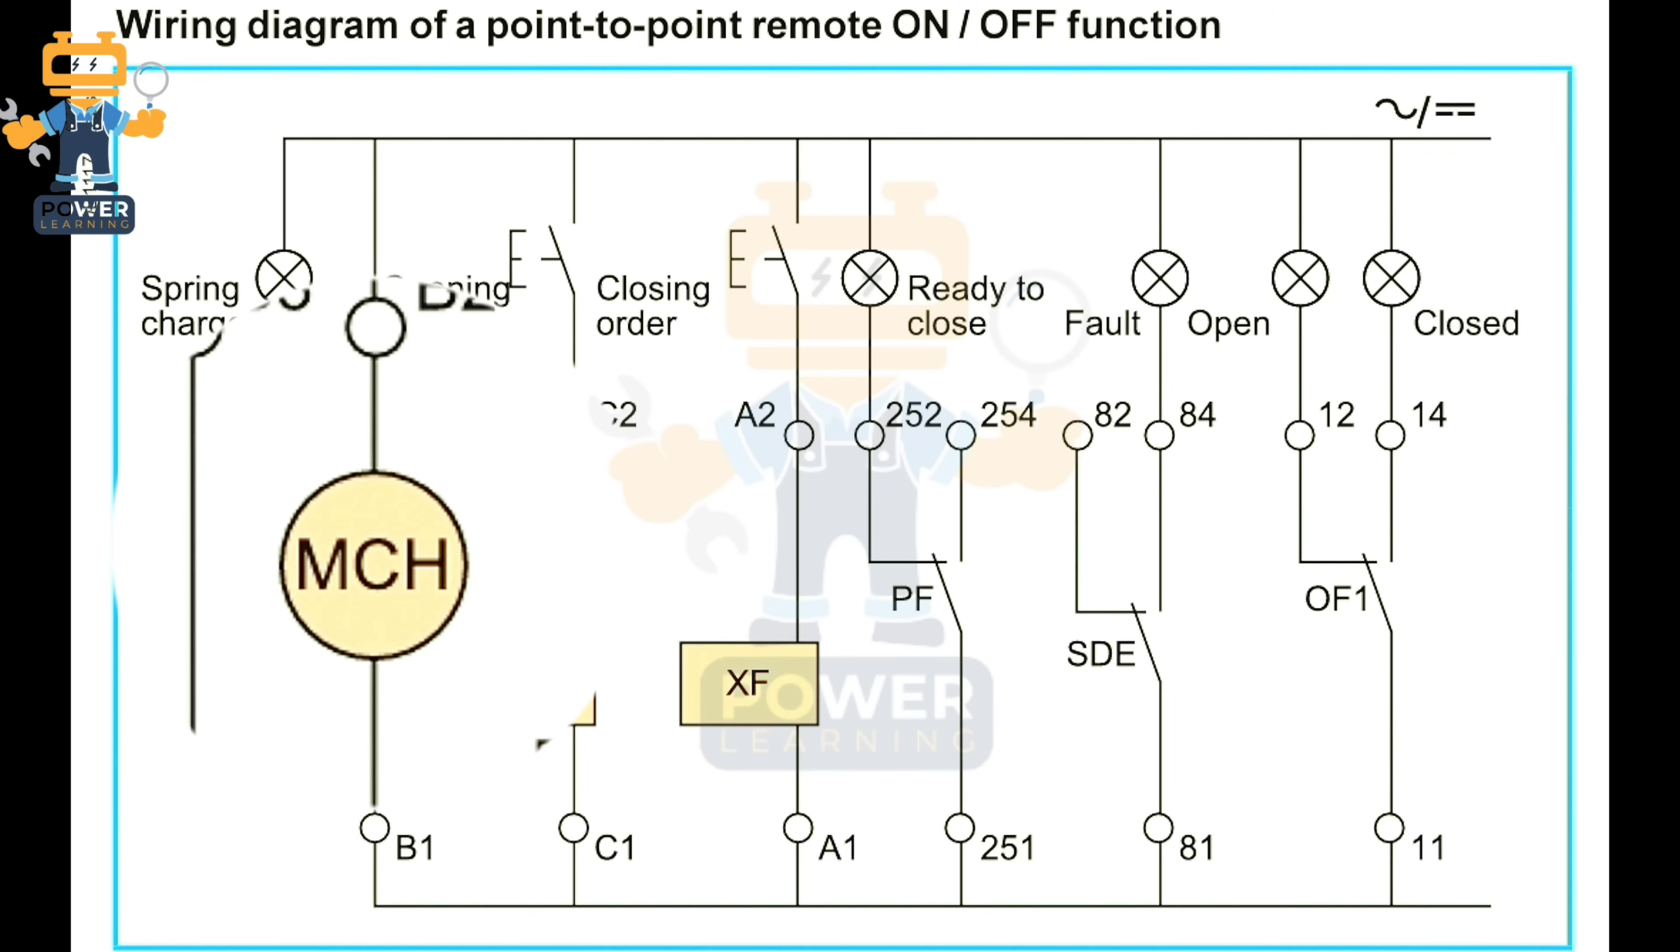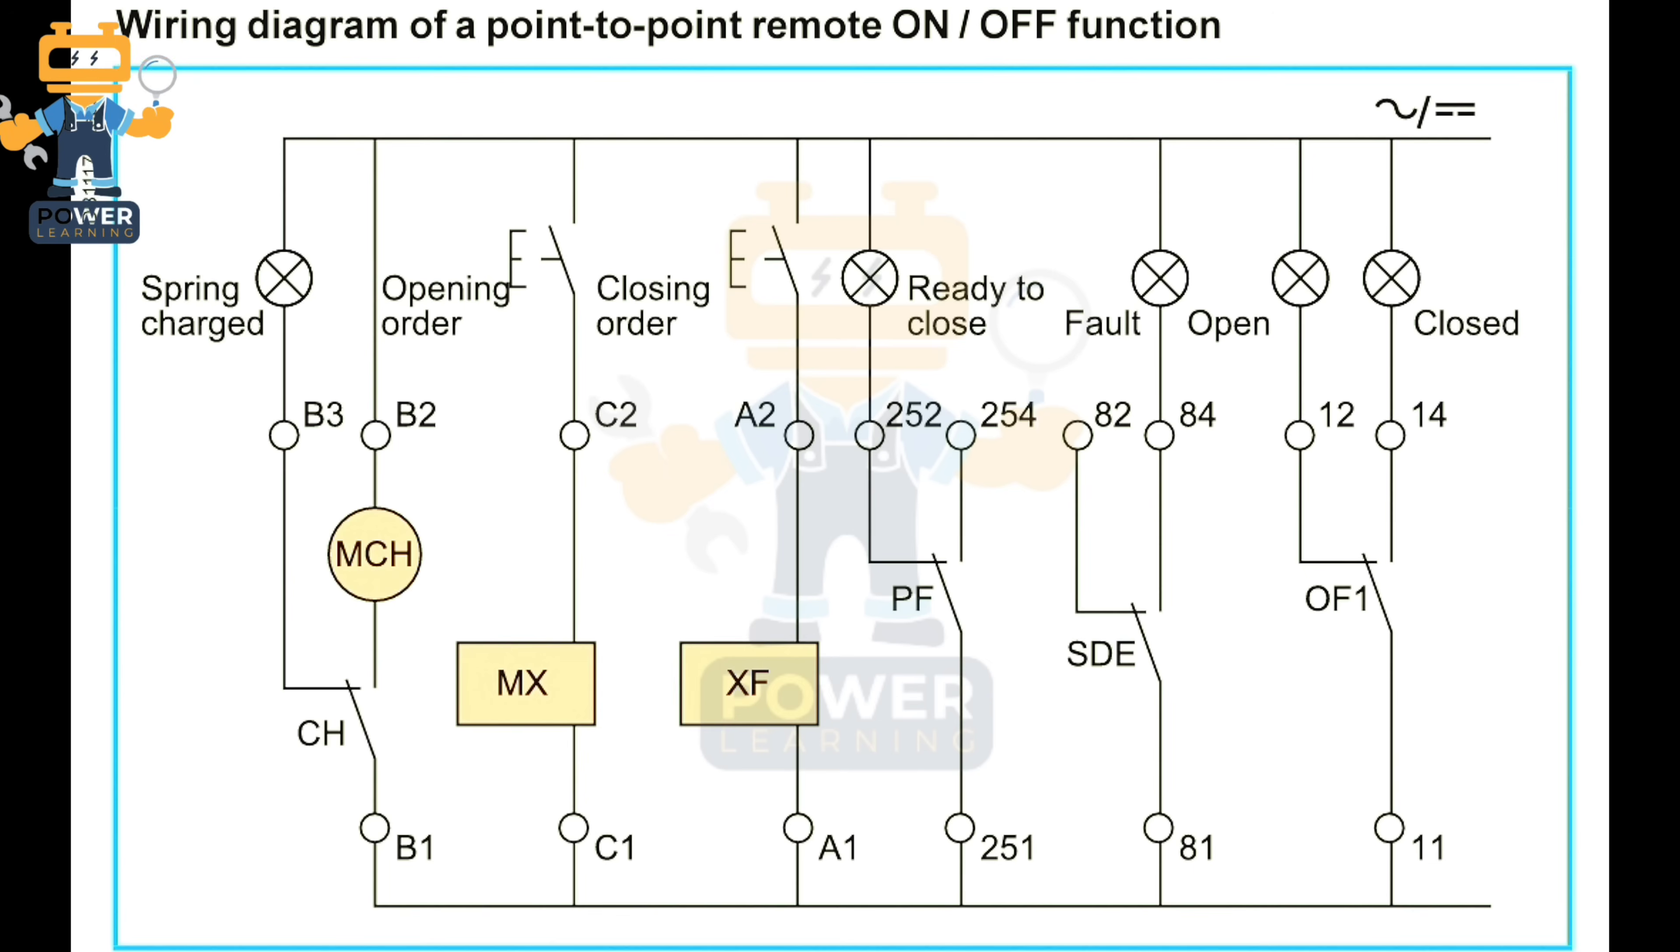Now in front of us we have the point-to-point remote ON/OFF function wiring diagram of our ACB. In ACB we first of all need to know what accessories we have which will help us to operate the ACB automatically. Now you see here we have first one symbol MCH, one is MX, and other one is XF. Other than this we have spring charged, opening order, closing order, ready to close, fault, open indication, and closed indication.